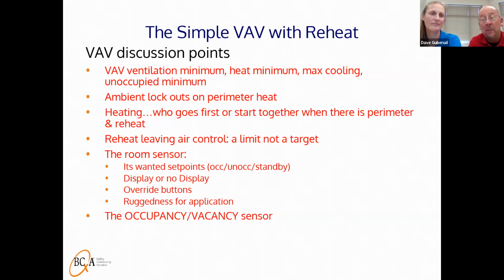because an unoccupied minimum is an important item when you potentially might have a 24/7 air handling unit, but a good portion of the zones are intended to truly go unoccupied. So you want that damper to truly go closed. The simple thing about ambient lockouts on perimeter heat: having perimeter heat on when it's 65 degrees or 70 degrees out here in Wisconsin is a very weird thing, but just locking it out at 55 degrees is a very simple thing.